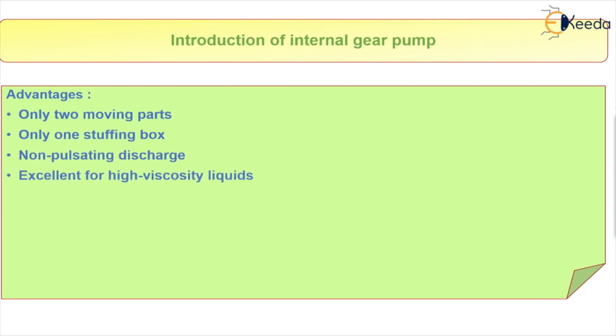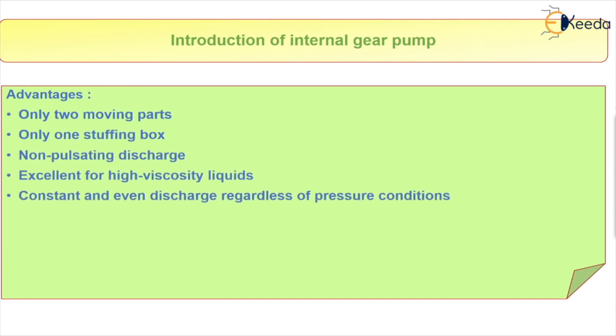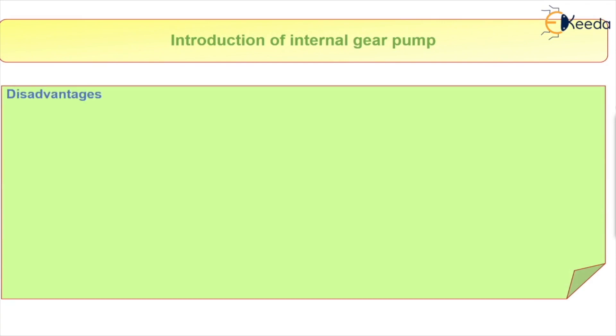Advantages of an internal gear pump: it has only two moving parts and one stuffing box. It has non-pulsating (constant) discharge. It is excellent for high viscosity fluids, and provides constant and even discharge regardless of pressure conditions. It also operates well in either direction.